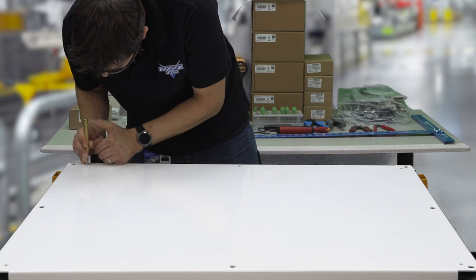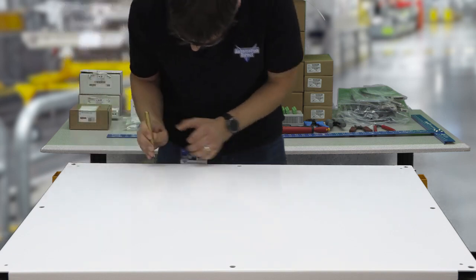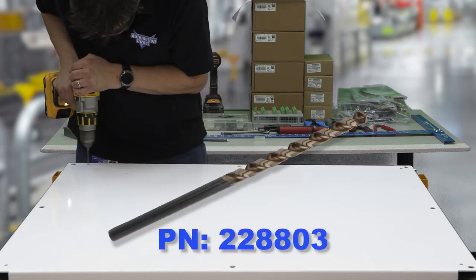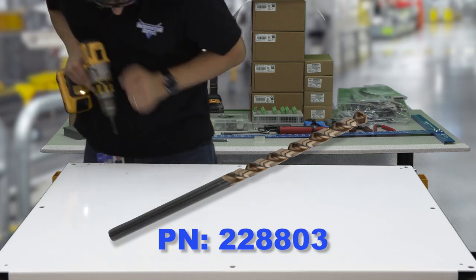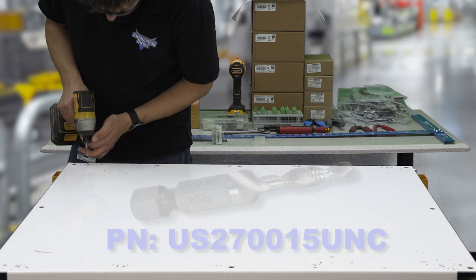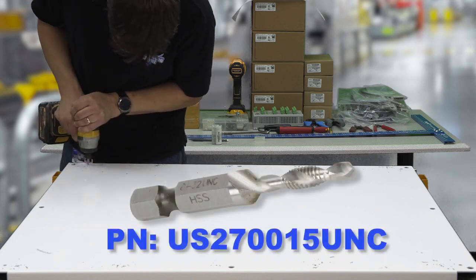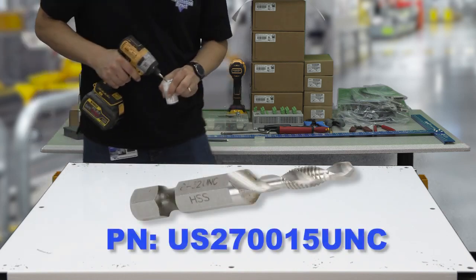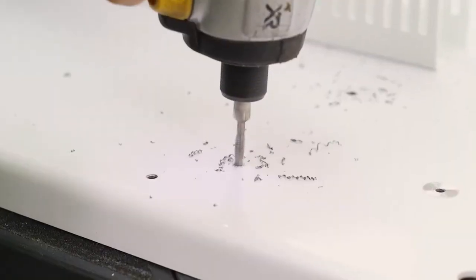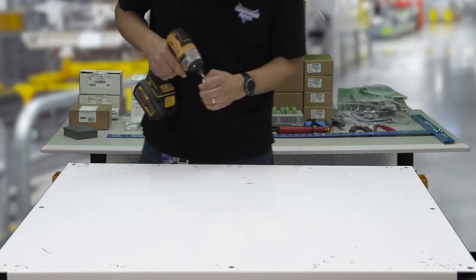Use a center punch to mark a divot in the center of each hole marked. Then, using a number 40 or 3/32 drill bit, drill pilot holes. Cutting oil helps keep the drill bit cool and sharp. Using an 8-32 drill tap bit and plenty of cutting oil, cut threads in every pilot hole that will be used to attach wire duct and DIN rail.